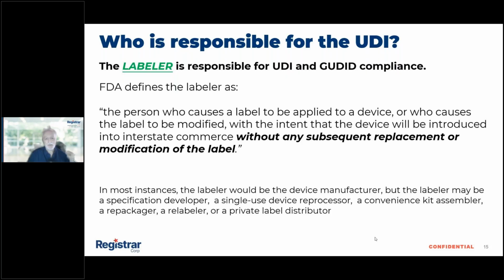In most instances, the labeler is really a device manufacturer, but the labeler might also be a specification developer, a single-use device reprocessor, a convenience kit assembler, a repackager, a relabeler, or a private label distributor. What makes you the labeler? To give you a better idea, if your company name is on the label, and if I would go into a real retail store and buy your device, and I would see a brand name and a company that is associated with that product, that should usually be the labeler and the responsible party for the UDI.